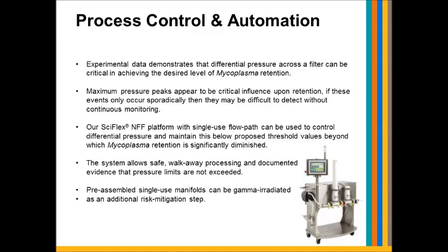pressure peaks that occur in processes can be controlled so that you avoid pressure spikes or having a process run up to greater than half a bar pressure differential, which we think is important both for maximizing your throughput of filtration but also for the retention of mycoplasma.